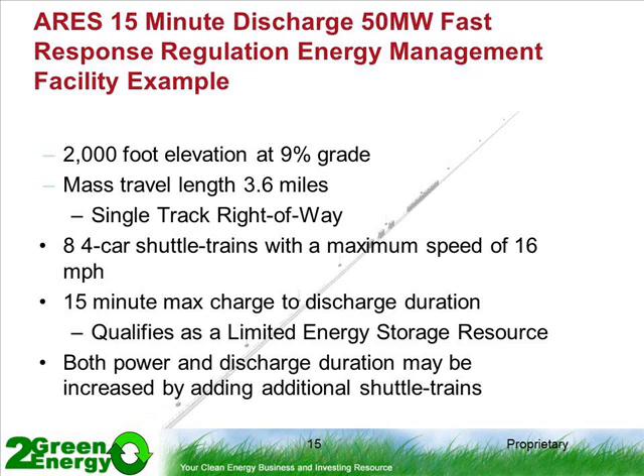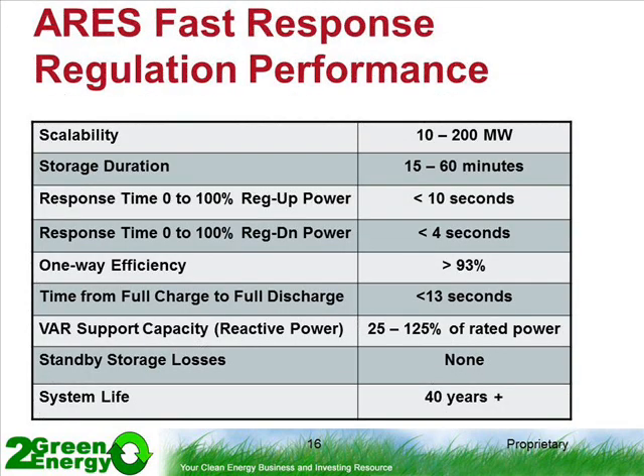And so the numbers there? Here's the numbers for an ancillary services machine. Again, you can go smaller—these are fundamentally smaller because they're single-track installations, ranging 10 to 200 megawatts, with shorter duration to stabilize the grid: less than 10 seconds to come up to full power, less than 4 seconds to regulate down, and one-way efficiency over 90%.